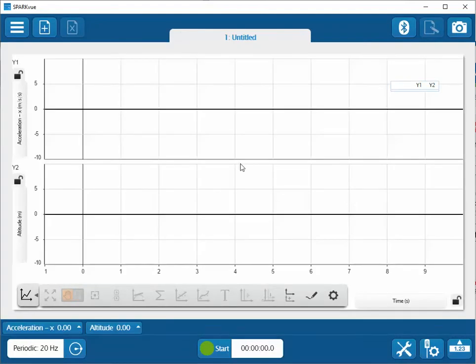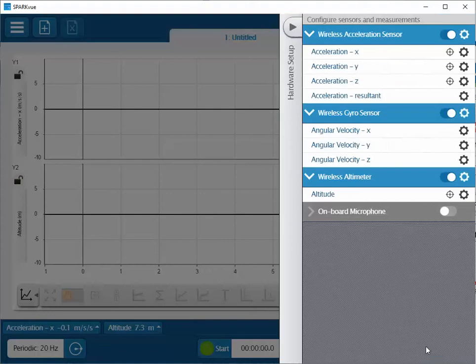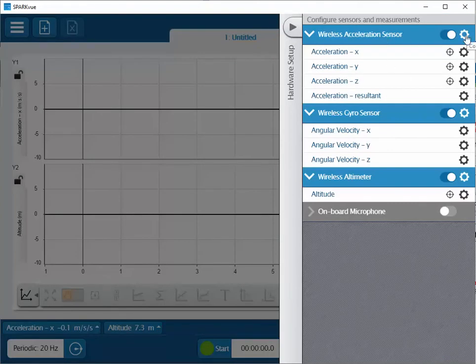One setting that can be configured for the sensor is the maximum acceleration range to be monitored. To do this, select the hardware setup button at the lower right-hand side, then select the wireless acceleration sensor and the gear icon on the dark blue line.